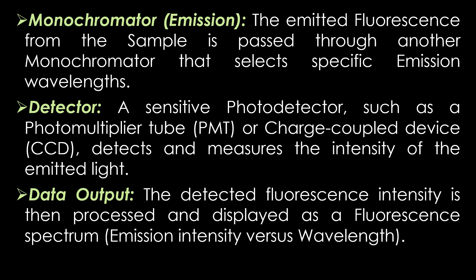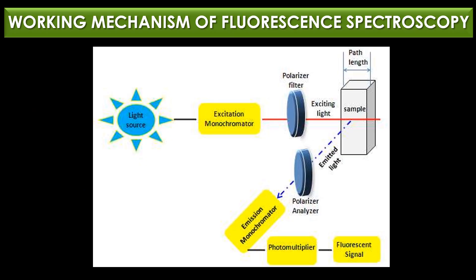The emitted fluorescence from the sample is passed through another monochromator, called the emission monochromator, which selects specific emission wavelengths. A sensitive photodetector, such as a photomultiplier tube or charge-coupled device, detects and measures the intensity of the emitted light. Finally, the detected fluorescence intensity is processed and displayed as a fluorescence spectrum showing emission intensity versus wavelength.